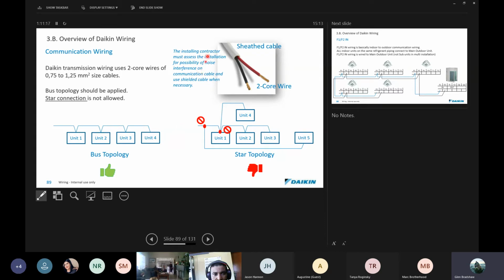Okay. The installing contractor must assess the installation for possibility of noise interference on the communication and use shielded cable when necessary. Okay, so up until VRV4, it has not been compulsory to use a shielded cable, but you will know that when we move into VRV5, it's going to become a compulsory aspect. It's in the training notes for VRV5 already. So my feeling about it is that if you are in an environment where you suspect that there might be noise interference on the cable, and this can come from fluorescent lights, it can come from X-ray equipment in a hospital or scanners in a hospital, Wi-Fi repeaters can also cause problems. Your voltage cables and your incoming power supply cables in a building, when you are installed very close to them, can be an issue as well.